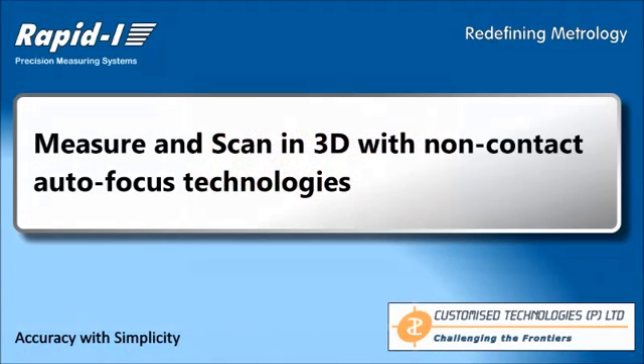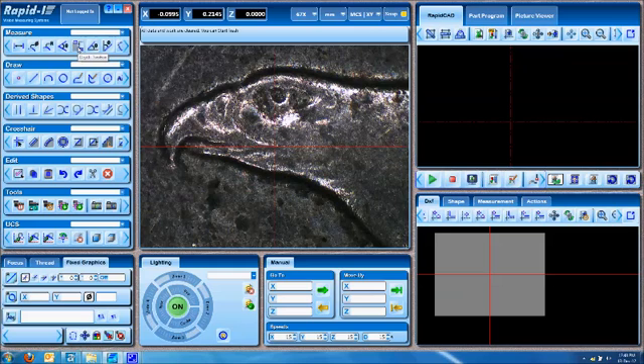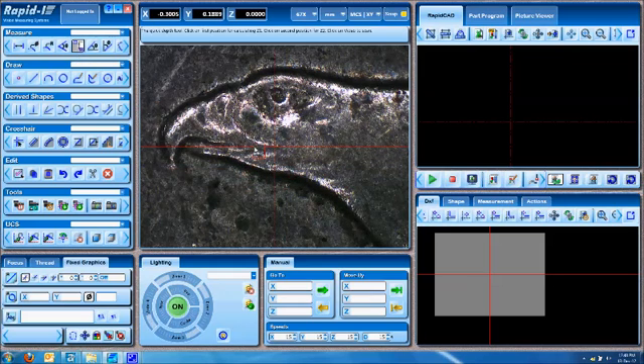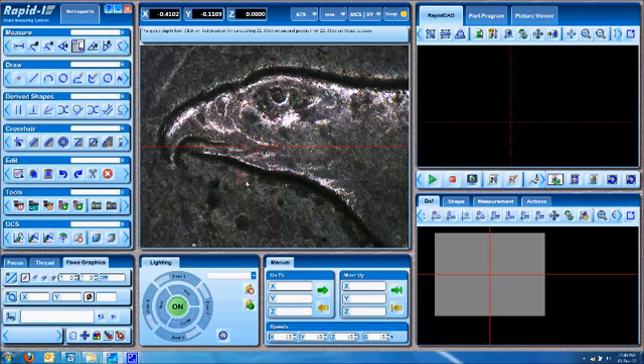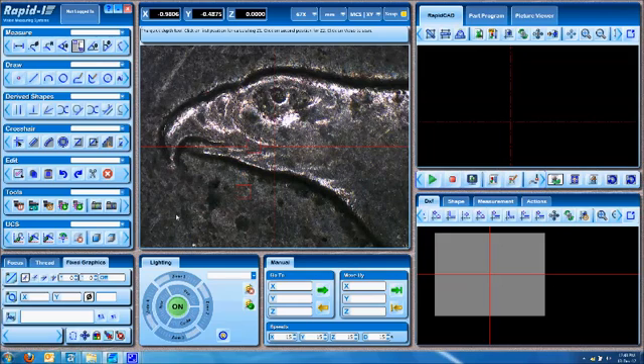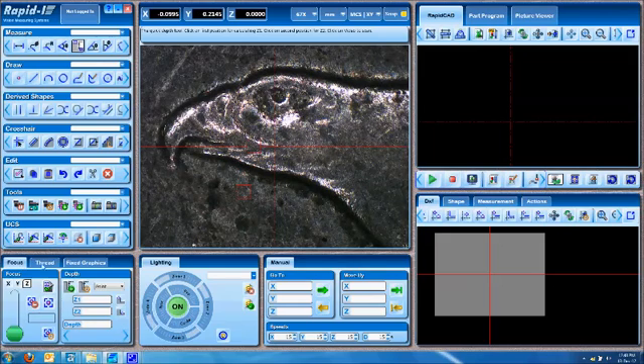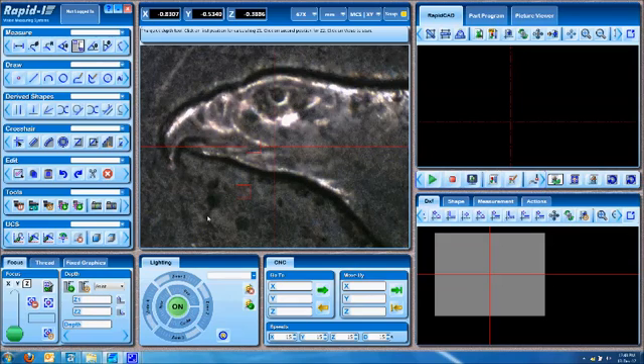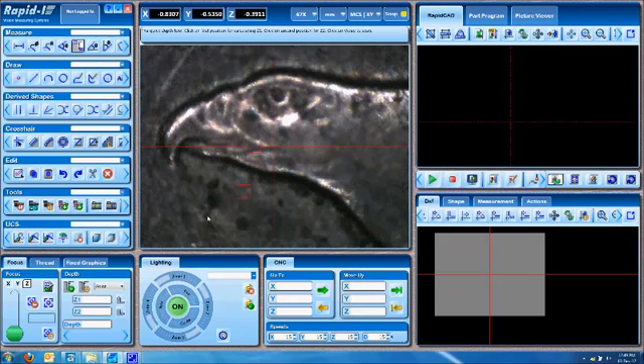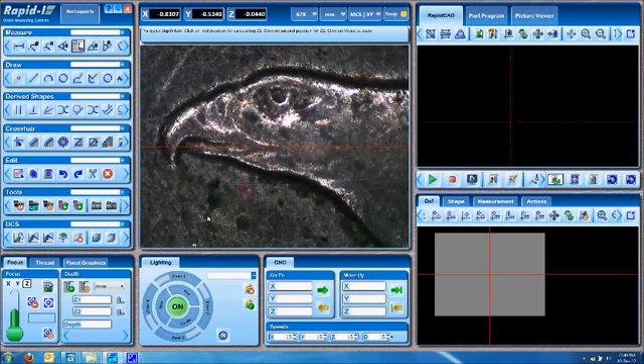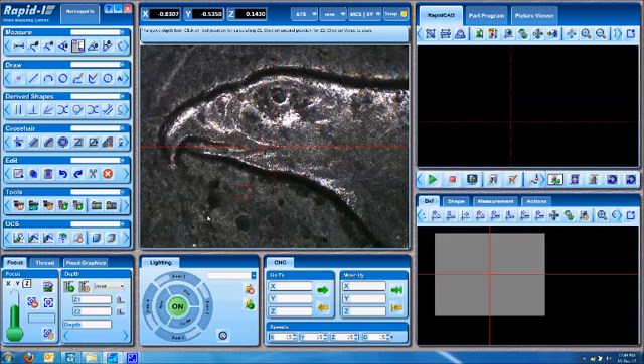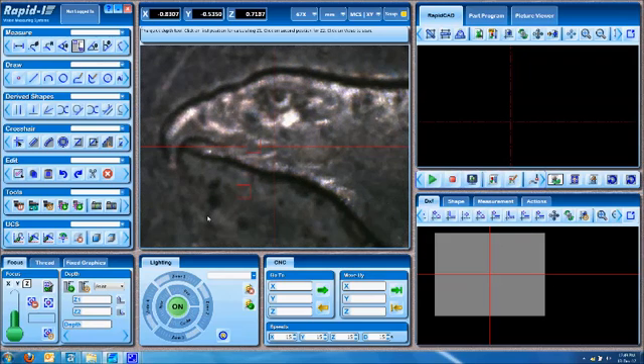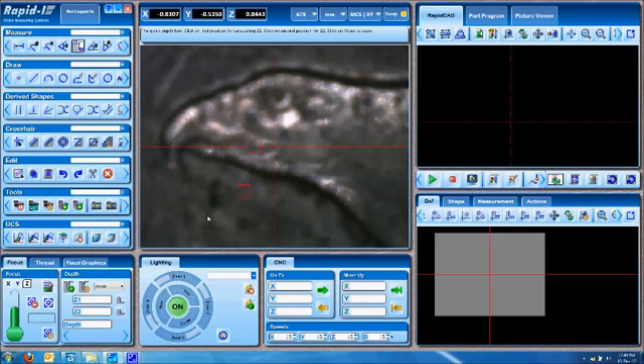If you want to measure the depth of the emboss of the eagle, just click on a point on the eagle's beak and one point on the base nearby. Then click on the video - it scans in the Z-axis. You can see on the bottom left it evaluates in real-time what's the level of the focus. As the focus happens, it calculates the best Z position for the two boxes.